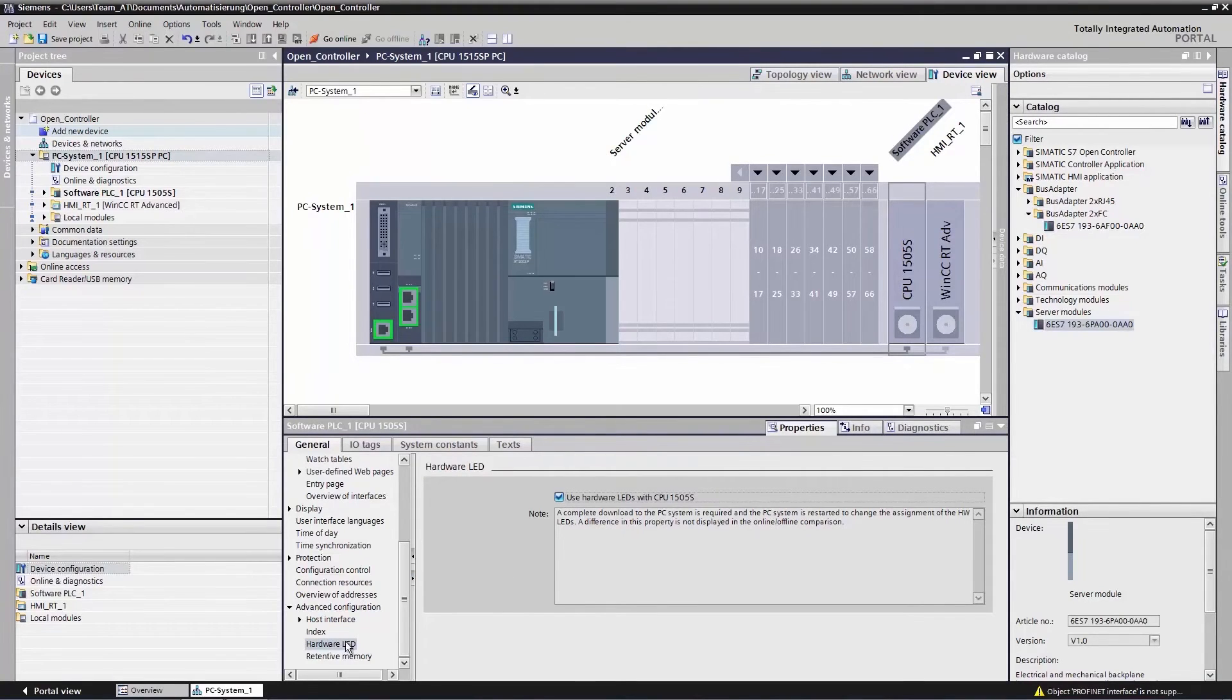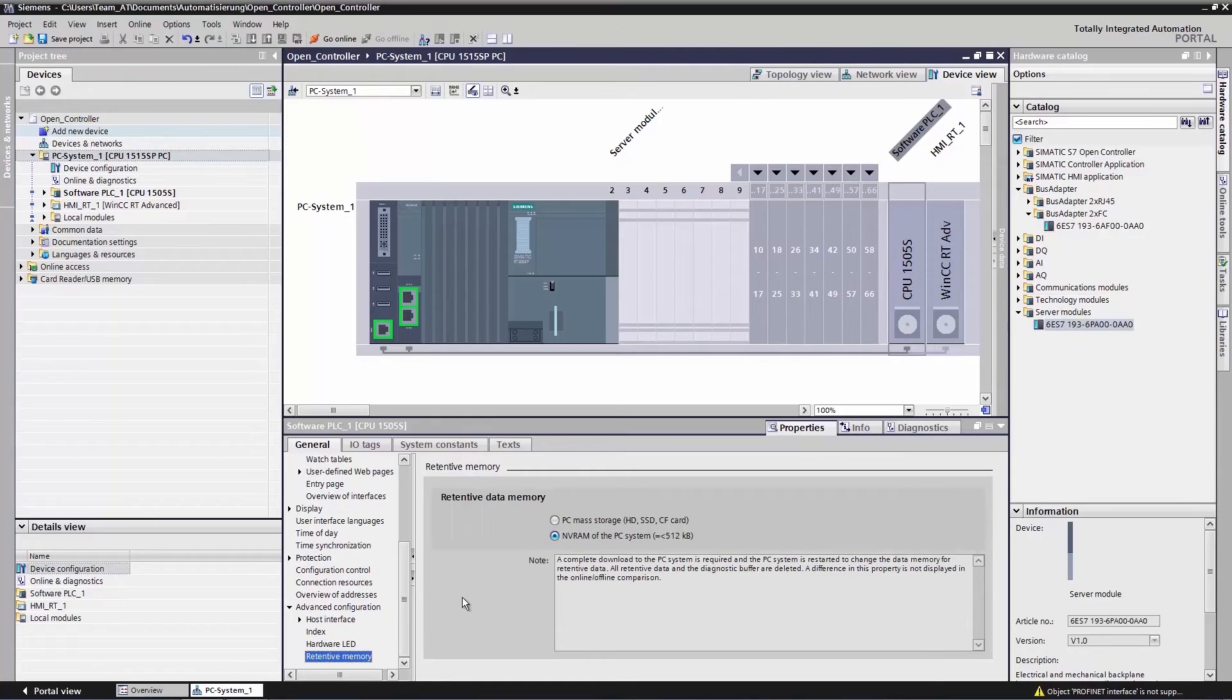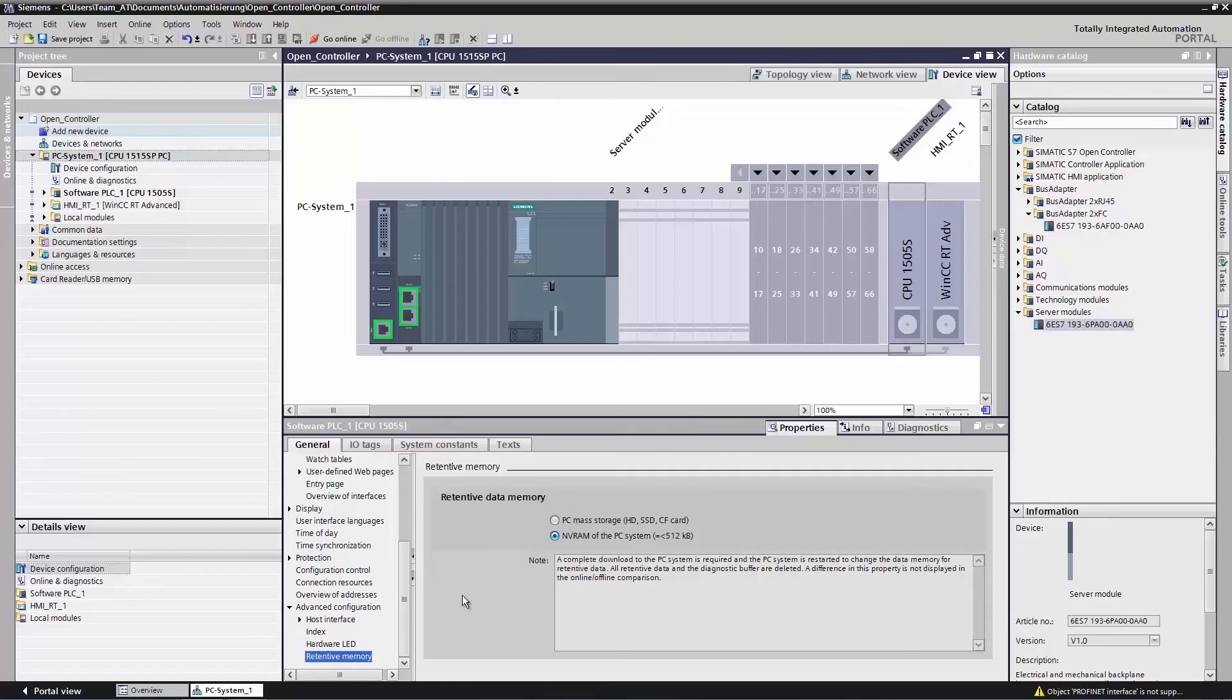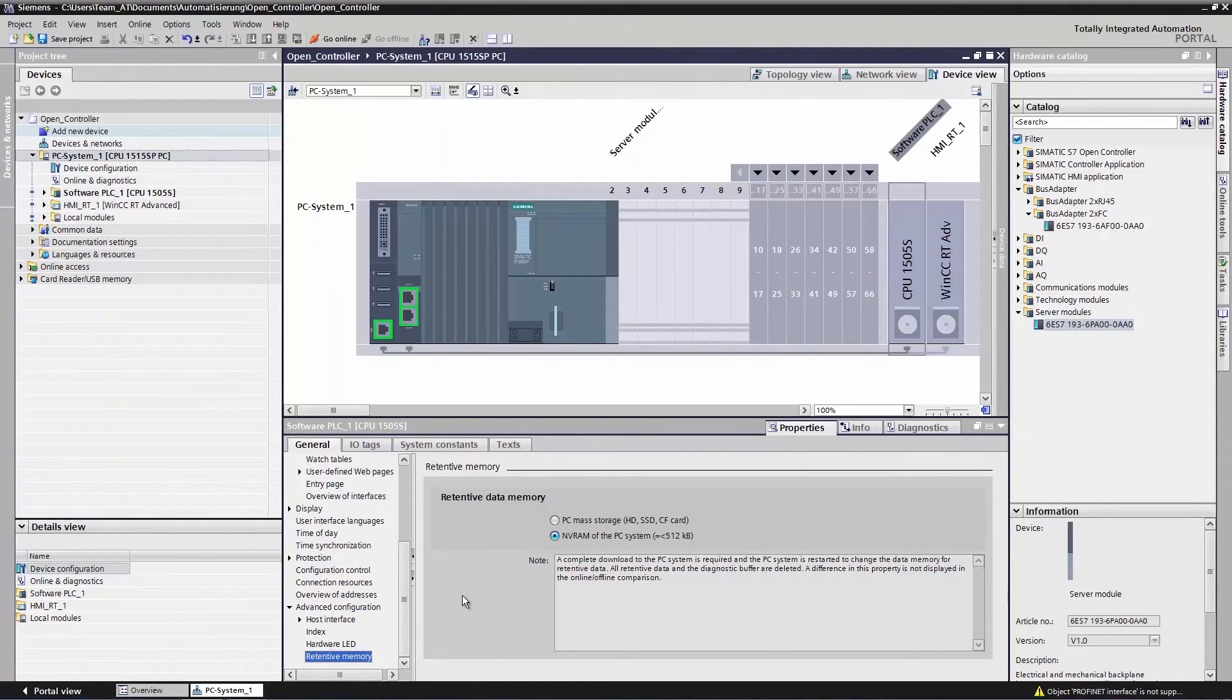As a last option, you can decide to store your buffered data in the mass storage or the embedded CPU RAM. Embedded RAM is a non-volatile memory where up to 512 megabytes of data can be stored. The data will still be available after voltage failure or disconnection.